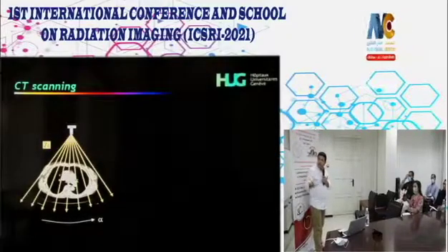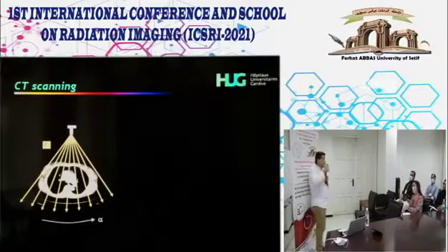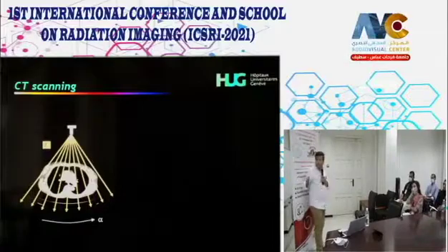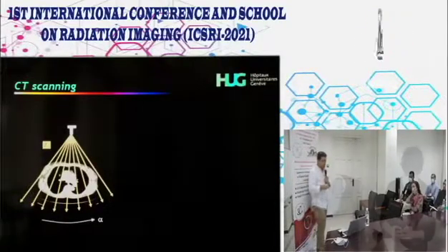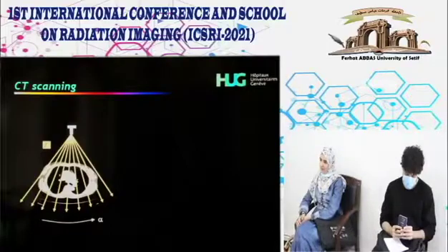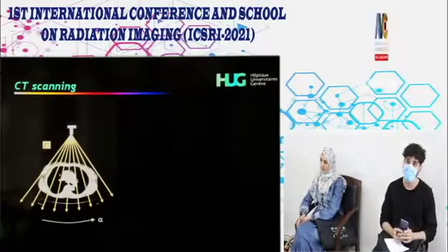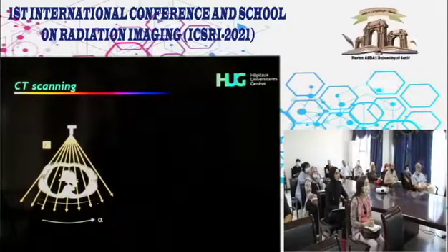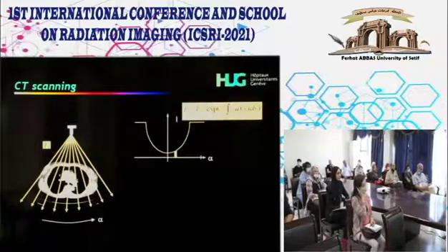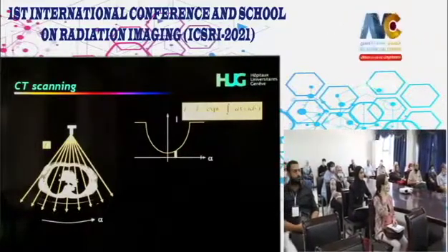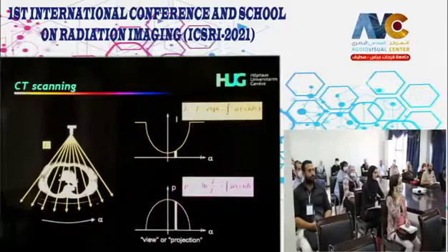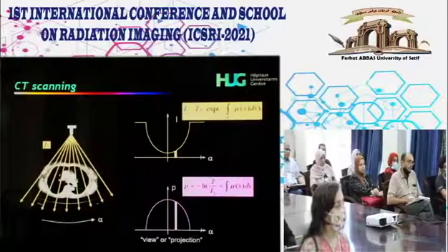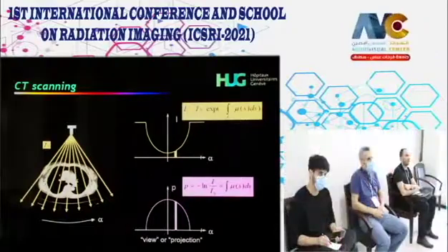And the idea is you've got an X-ray tube here, what you see at the top, and a bunch of X-ray detectors on the opposite side of the patient, right? And then you collect the data in fan beam mode, right? And then we collect the projections that you see here, with exactly the same formula that you have been introduced to previously. And then we take the logarithm of the projections. This is the first step before we proceed to image reconstruction.